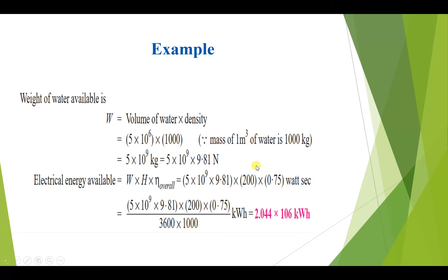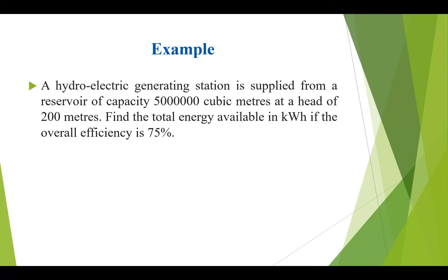Since the result is in watt-seconds, we need to convert to kilowatt-hours — dividing by 1000 to convert watts to kilowatts and by 3600 to convert seconds to hours. By simplification we get 2.044×10⁶ kilowatt-hours. This is the total energy available for the hydroelectric station with a reservoir capacity of 5×10⁶ m³, a head of 200 meters, and 75% efficiency.